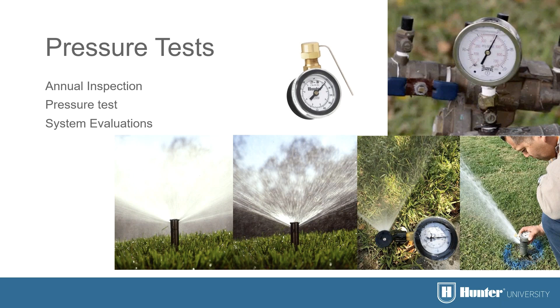Yeah, I really like the idea that you guys shared earlier, Brian or Chris mentioned it, of having that sticker inside of the controller that says who the system was designed by. Maybe another piece of that information, which I would find really valuable, is knowing what the incoming pressure was supposed to be when the system was designed, because gradually over time, we do find that pressure does decrease. And if you're using a system that has flow sensing, the decrease in pressure is going to completely throw off your flows from season to season. So if you do believe that pressure has decreased, it's probably good practice to start checking flows and pressure at the beginning of each irrigation season, and if the pressure is decreasing, after you do a full system check and make sure everything's running properly, doing a complete learn flow on all your zones again.